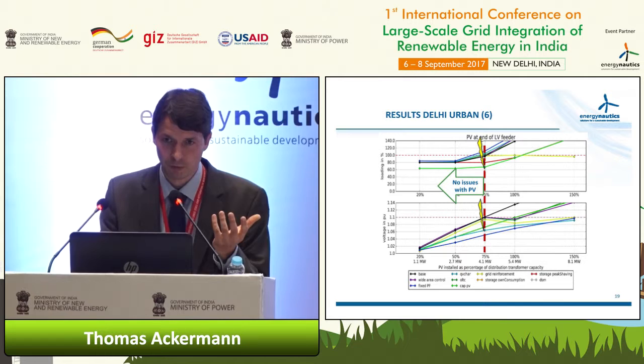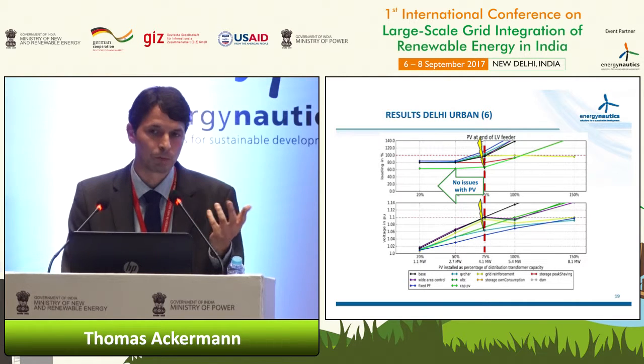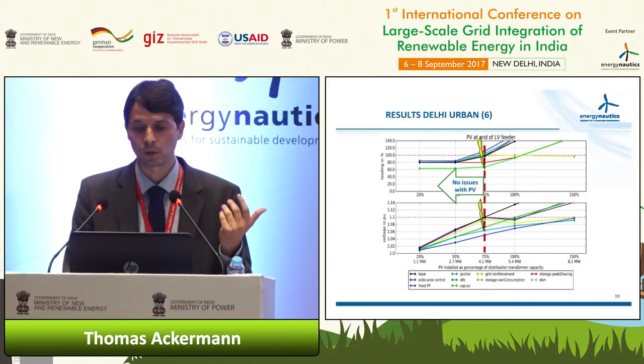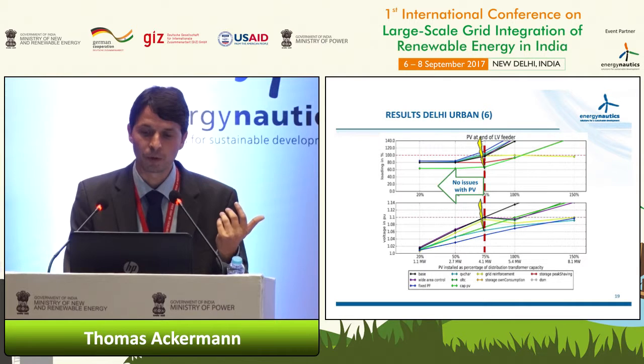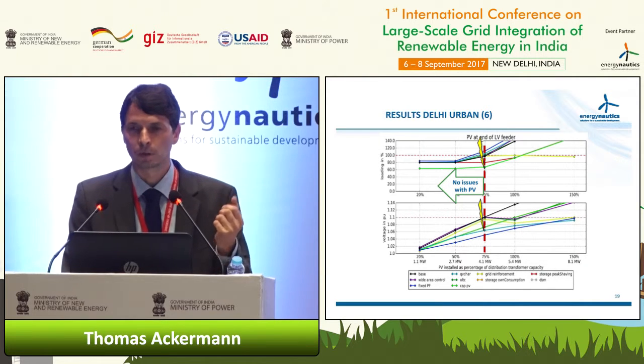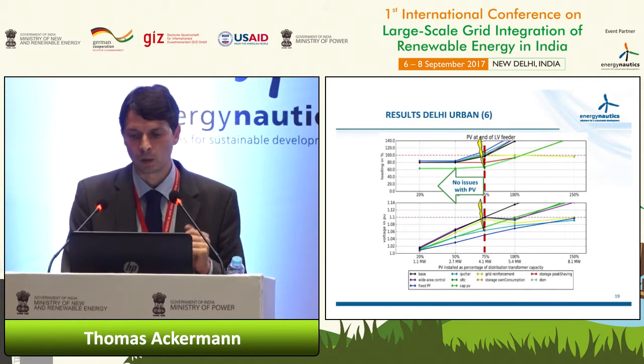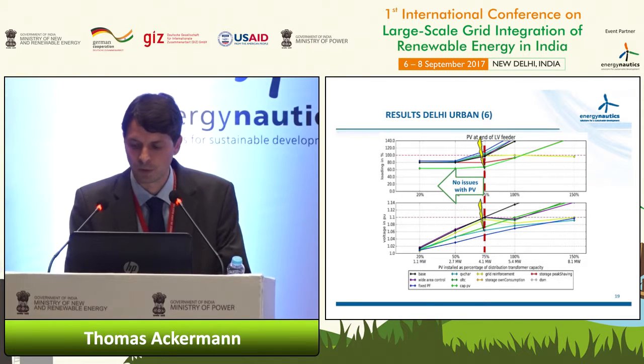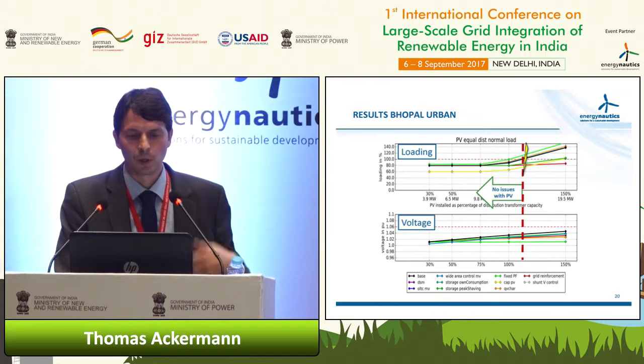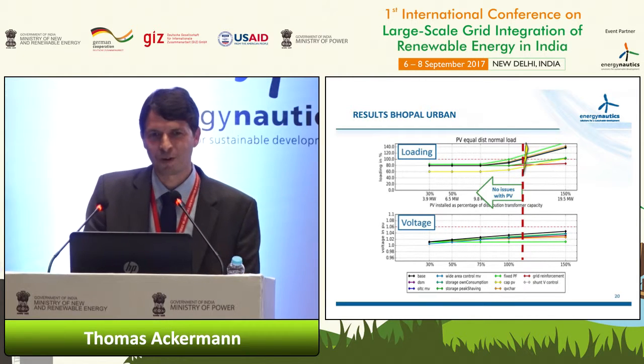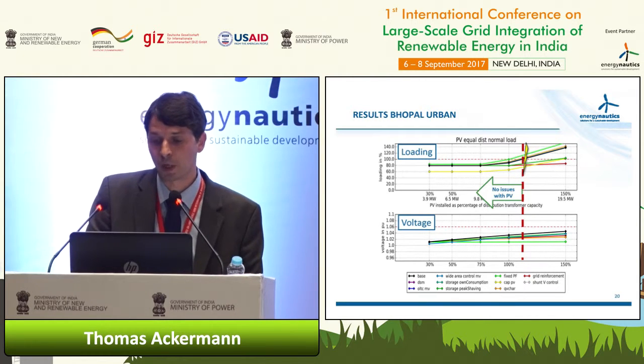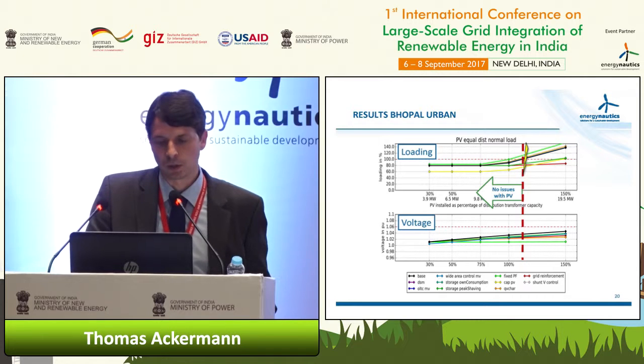So we don't have a voltage issue here, but using reactive power would worsen the situation. So here it's only helpful to use active power measures, so capping or using batteries, for example. Those are the solutions we do see. Looking at BHOPAL, this was a pretty strong grid, so we are above 100% when reaching the limit.